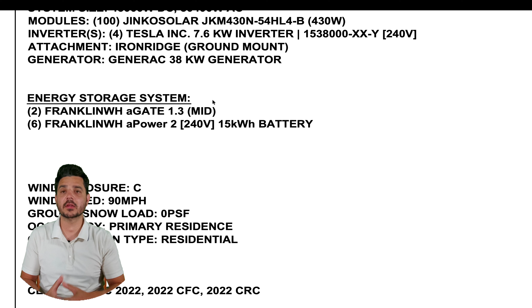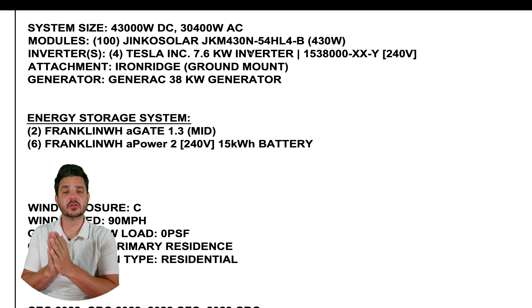Now with the aGates with Franklin, the maximum you can back up is 64 amps continuous. So the system is split 50-50, literally 50-50. There are 2 Tesla Solar Inverters for each 50 panels, 25 and 25, and each one puts out 7.6 kilowatts, which gives us a total of 15 kilowatts AC.